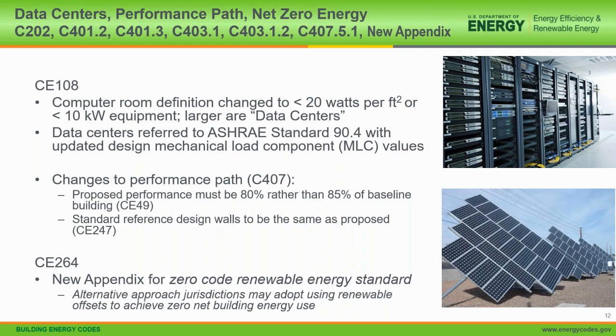So that takes it basically to a different standard. Now, be aware that that standard does refer back to 90.1 when there are questions about, like, an office area inside a data center. Those areas would be covered by 90.1 requirements. So it's sort of like a back and forth reference, if you will. But this does make it clear what the boundary is between those, and it's pretty crisp. Now, there's also some additional information that's included there.